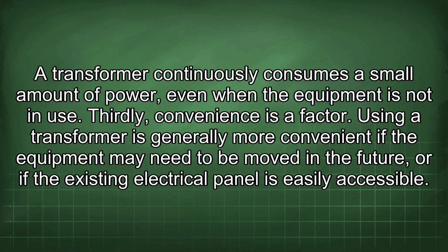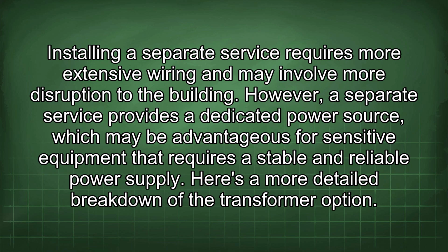Thirdly, convenience is a factor. Using a transformer is generally more convenient if the equipment may need to be moved in the future or if the existing electrical panel is easily accessible. Installing a separate service requires more extensive wiring and may involve more disruption to the building. However, a separate service provides a dedicated power source, which may be advantageous for sensitive equipment that requires a stable and reliable power supply. Here is a more detailed breakdown of the transformer option.